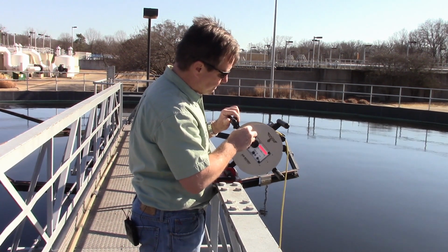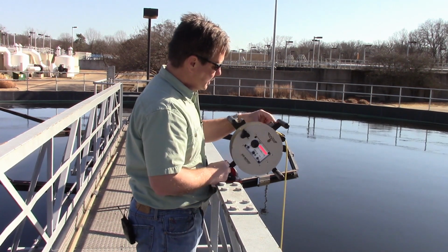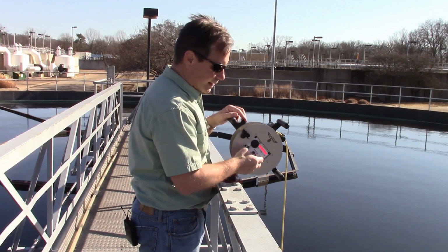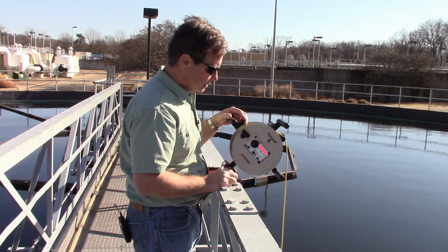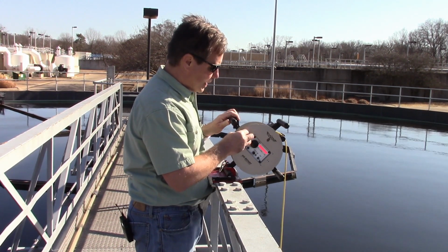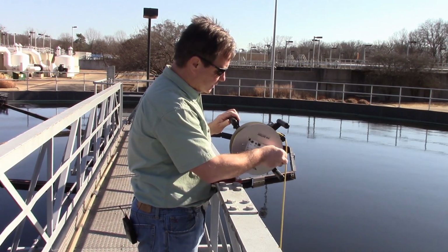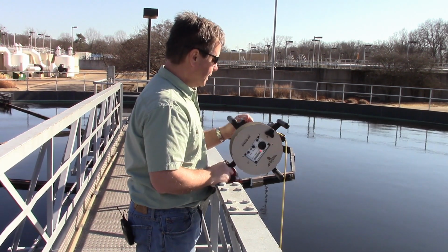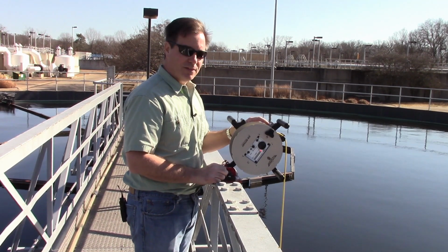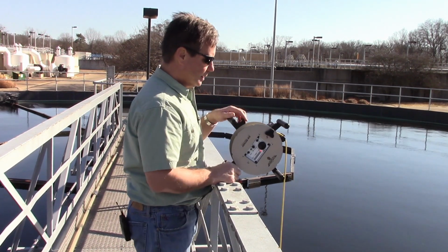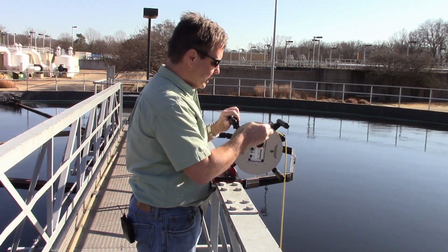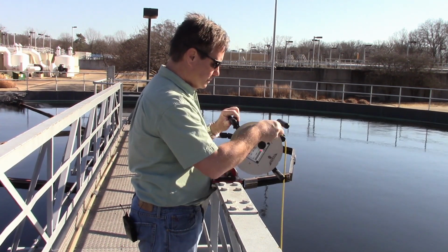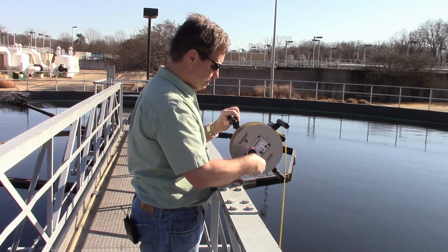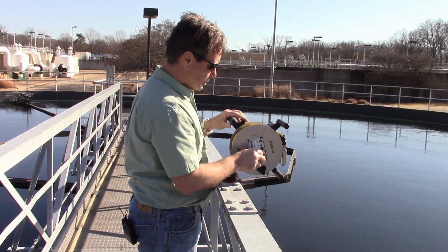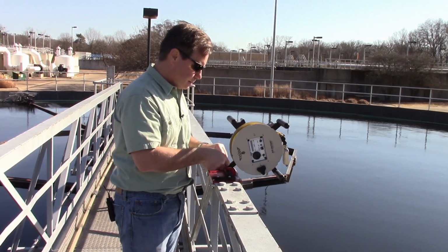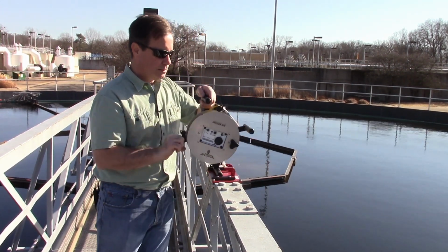Once at the bottom, I can tell the probe's on the bottom right there. I zero out the counter. All my lights are on because the probe is fully engaged in sludge. Then I pull the brake back and I reel it in until the lights go out right there. And I can tell by looking at the counter, I've got 11 inches of sludge in this tank. At that point, we make the note and reel it all the way in. Power down, and move on to the next tank.